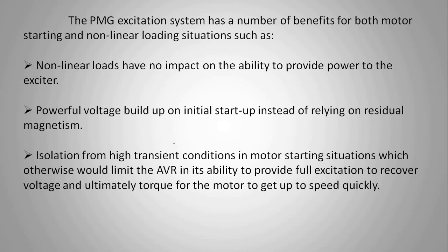In pumped storage plants, the same generator can be used as a synchronous motor to pump up and lift the water. In that case, the motor needs a very high starting torque, and the starting torque is a function of excitation. So there also the AVR plays the most important role.